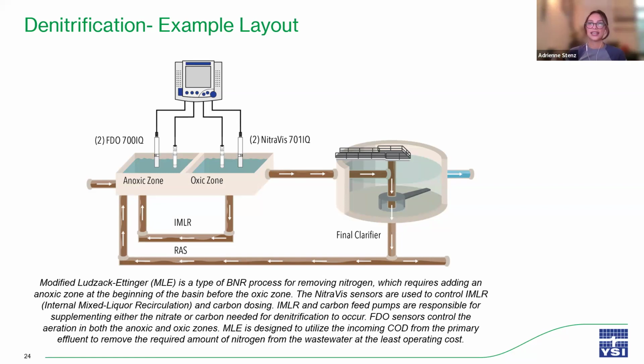Denitrification requires the correct amount of nutrients in the water to work effectively. So denitrification requires a ratio of 3:1 BOD to nitrate. And oftentimes, plants will have to dose carbon, often in the form of methanol, to get the right ratio of BOD to nitrate to perform denitrification in this zone. Oftentimes, optical nitrate sensors are used in these anoxic zones to measure nitrate and control the dosing of carbon in these areas.